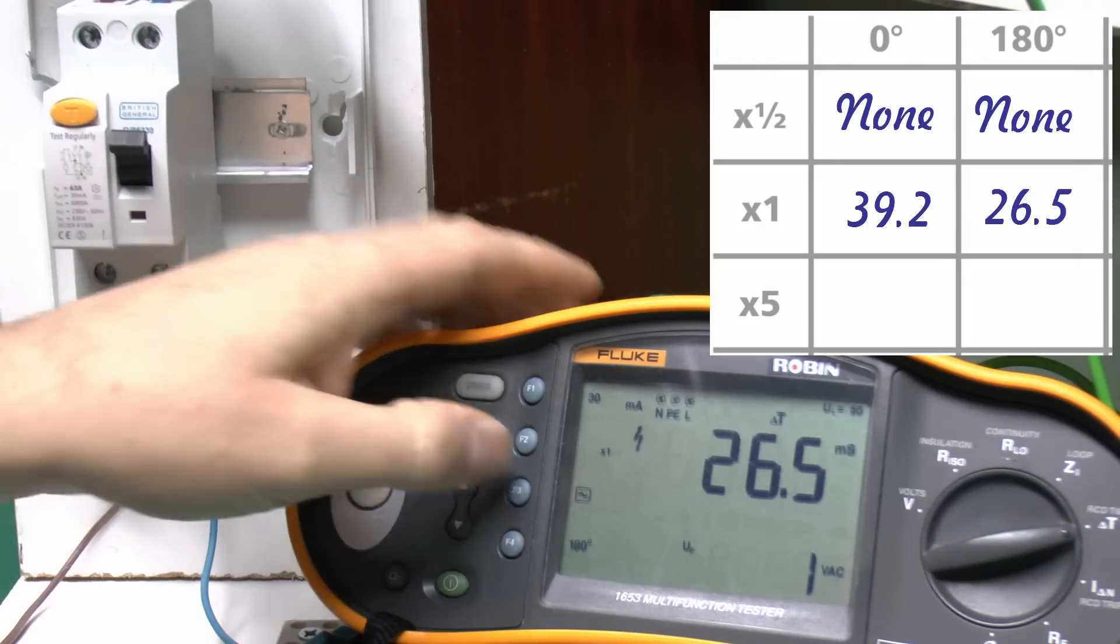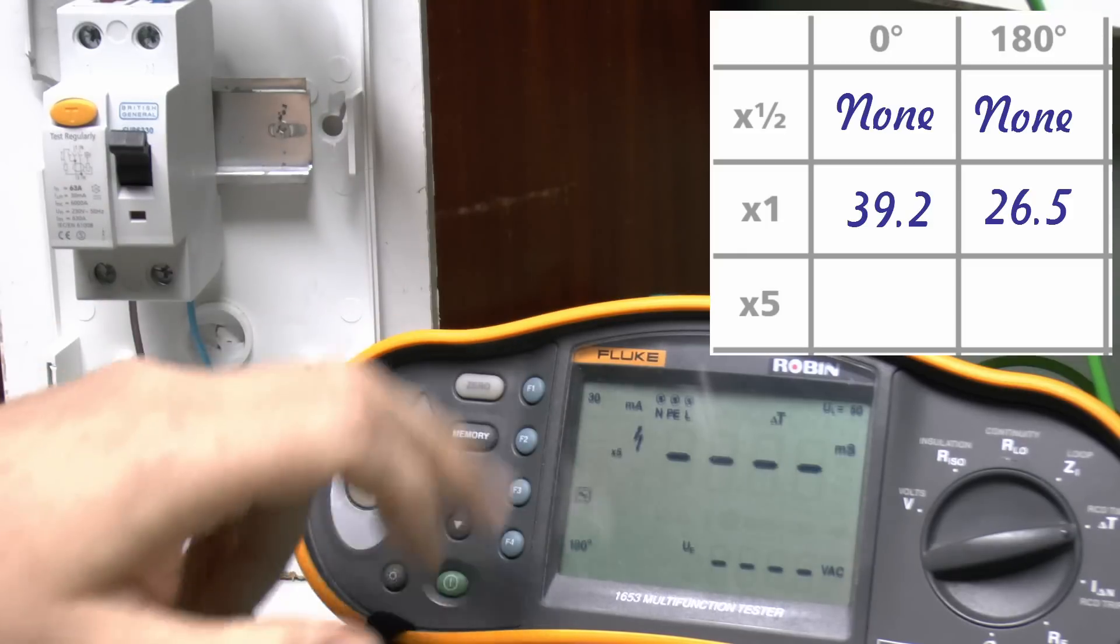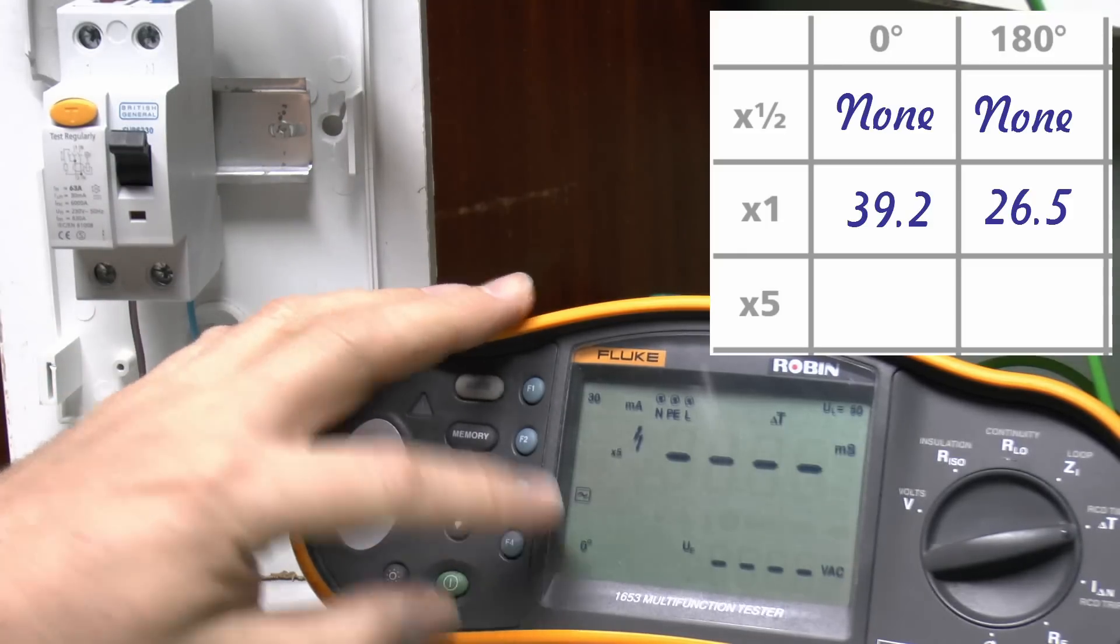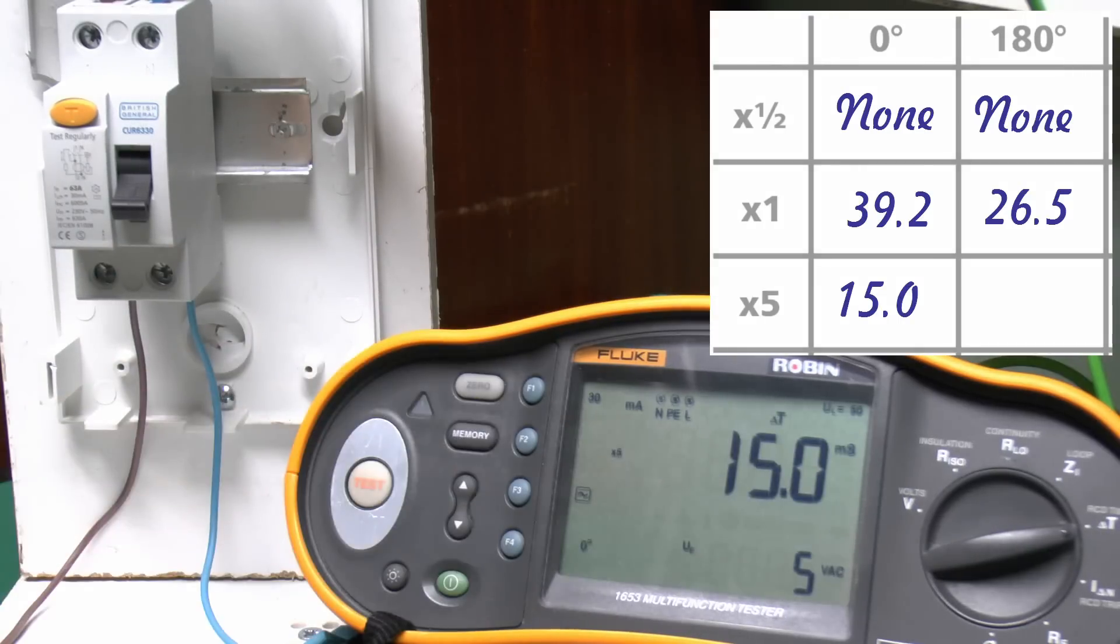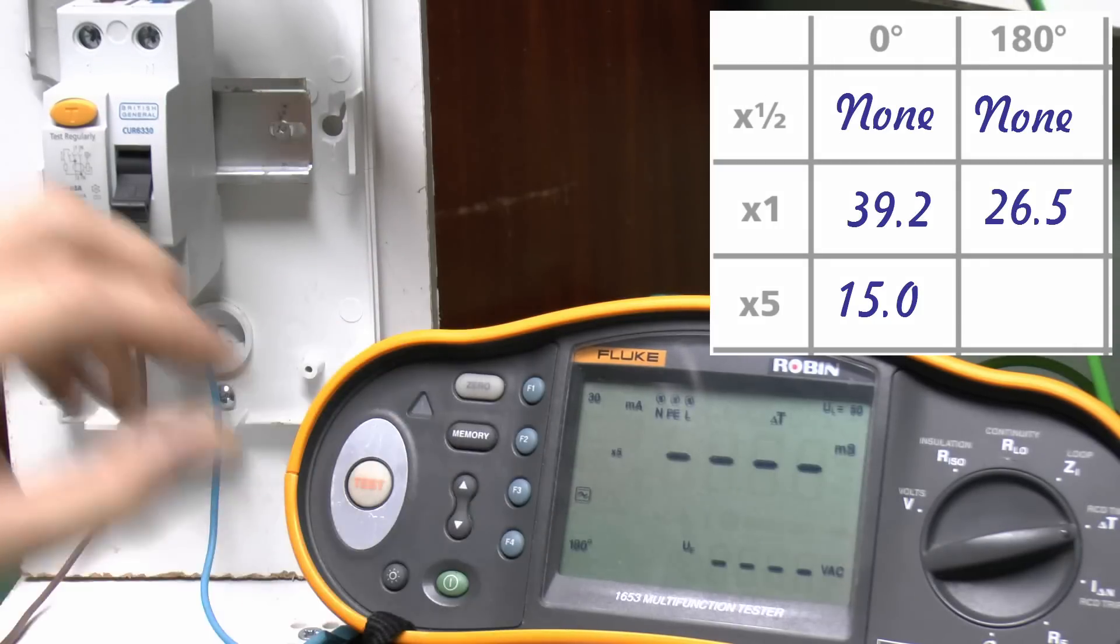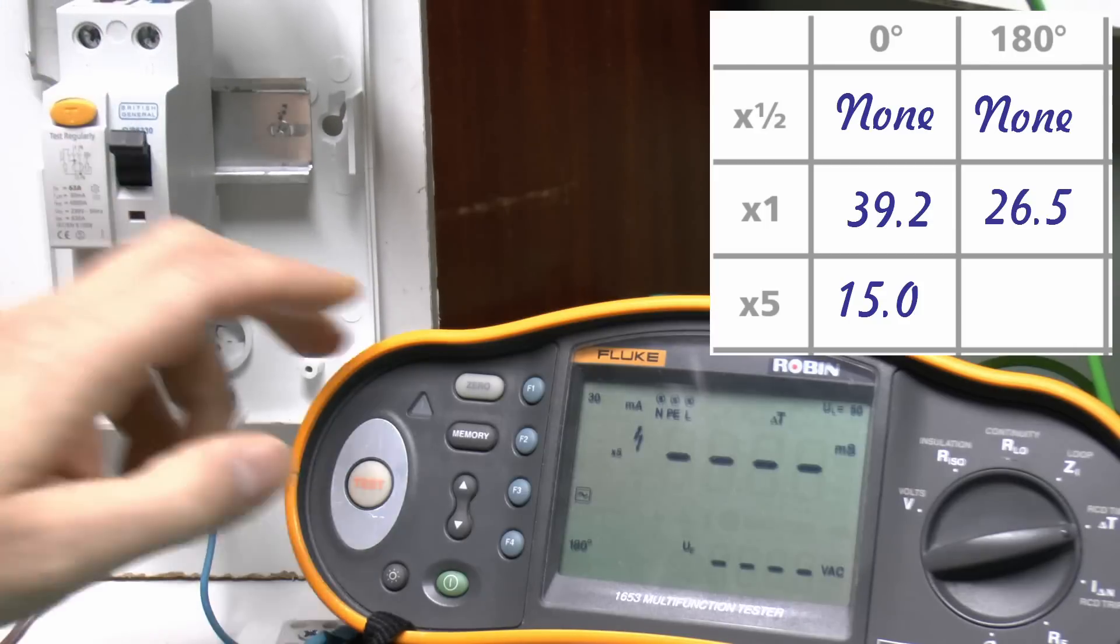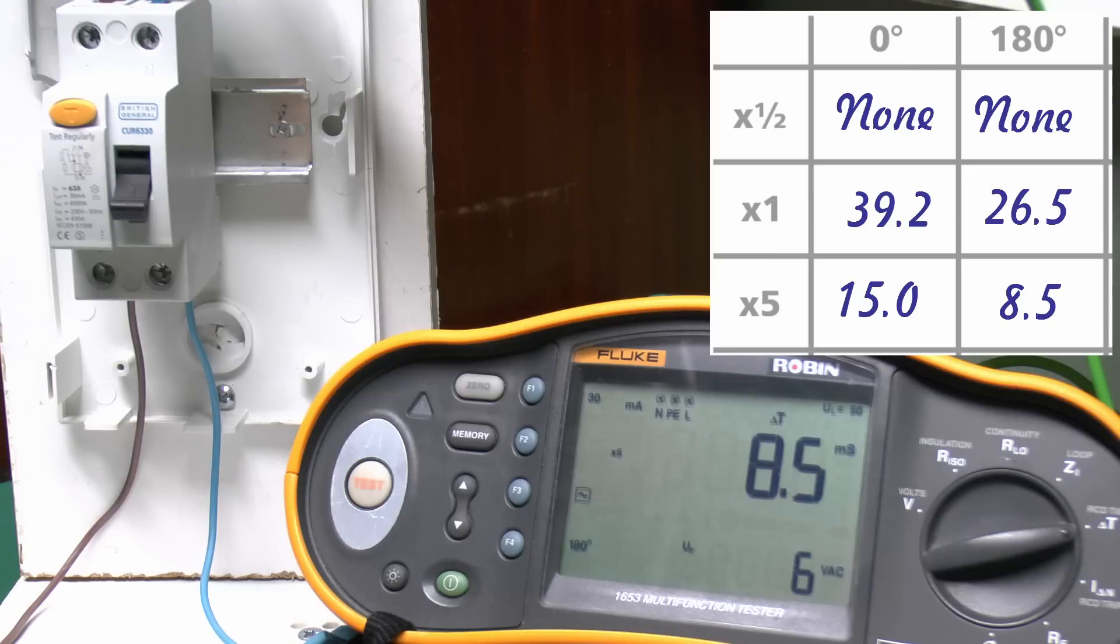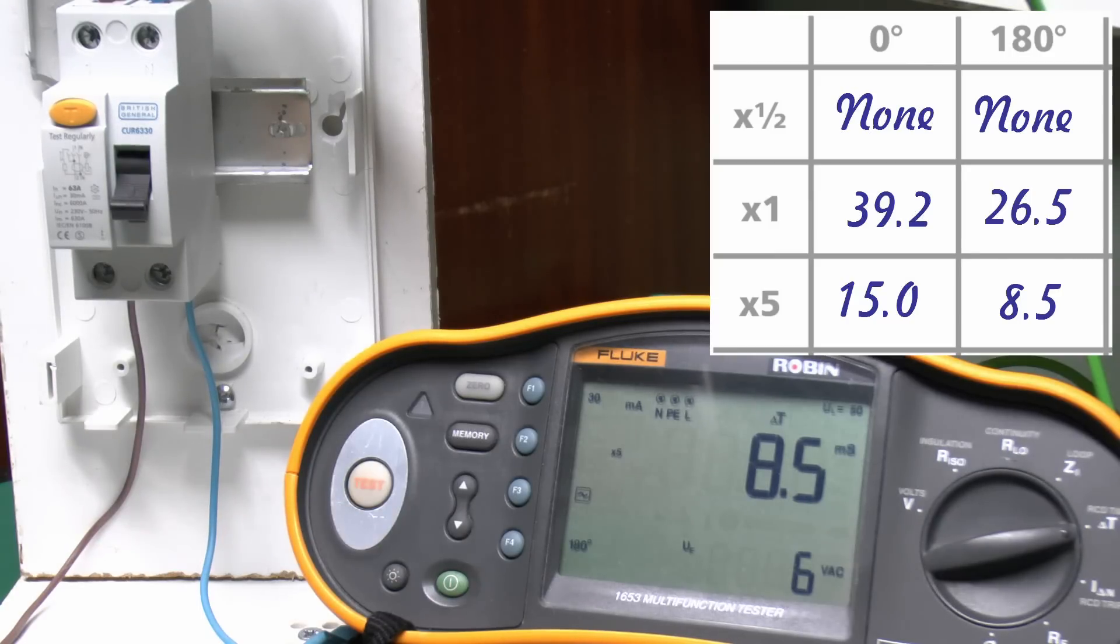So then we'll move on to the times 5, which will apply the 150mA setting, and again, we'll do that on the 0 to start with. 15 milliseconds, and on the 180 setting, 8.5. Notice there is quite a difference between the two settings there, hence why it's necessary to do them on both the 0 and the 180.